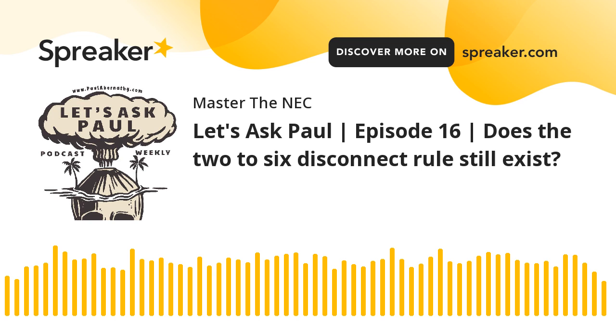And most people would say, well, Paul, maybe I'm just going to come up and hit a 200 amp main disconnect. And because those are smaller, thinner, narrower, and they're service listed for use as service equipment, or SUSE rated, and I'm going to stack them all right there. Perfect. Because once you get on the load side of those, then it's just feeders going through the building, and that's okay. Feeders can go through the building.